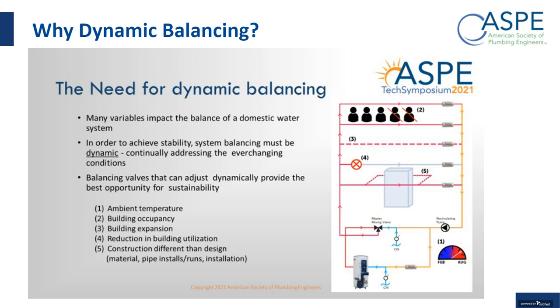So there was always pulling hot water into the system. So it really didn't need to be balanced because there was enough water being pulled into the branches or risers based on usage. But once people started coming back and you only had 20% occupancy versus 100% occupancy, now the usage was very low, and now you started seeing balancing issues. So another reason why you needed dynamic balancing.